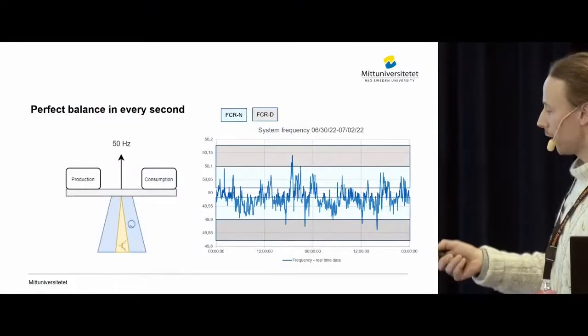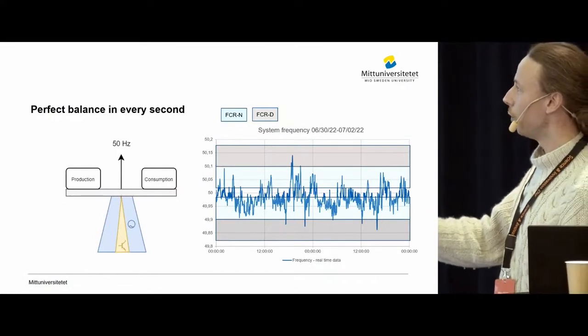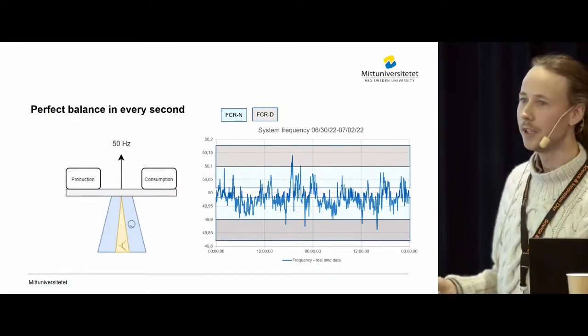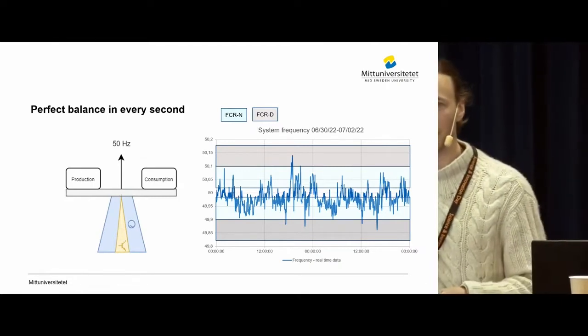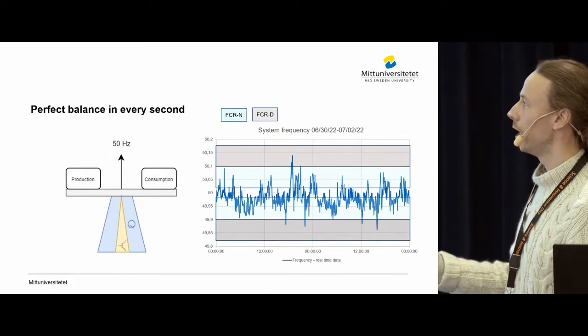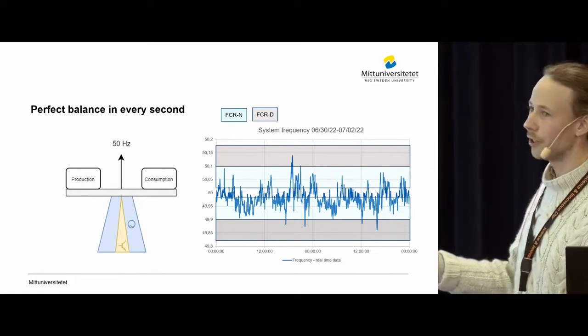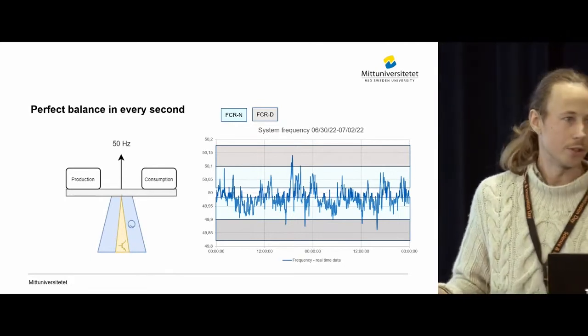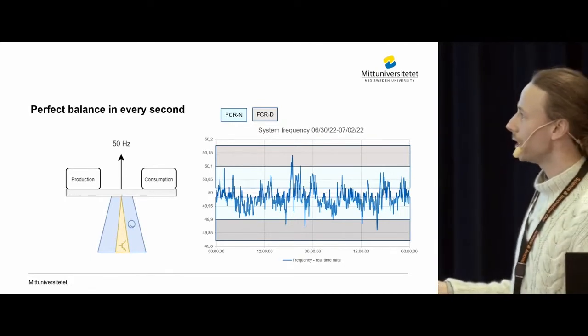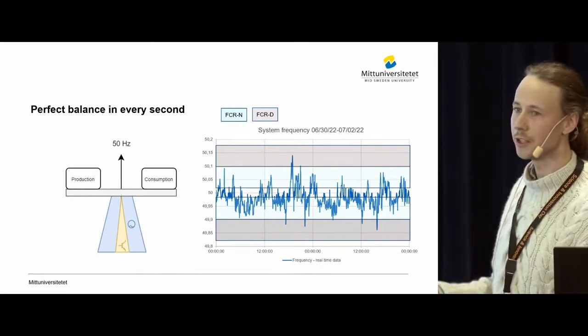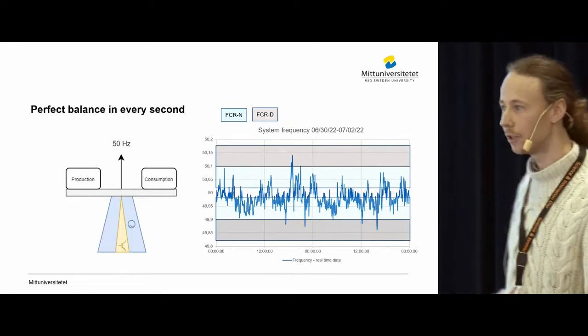We're talking about what's happening in the power system. We're getting more converter-based generation and less generator-based production. I've illustrated how this affects the change in frequency in this pedagogical scale with two different bases. A power system with lots of generators producing electricity has a wide base, so if there's a dip in production, the scale won't tip as fast. But with lots of converter-based generation, this base shortens, and the system needs to be balanced more actively and faster to counteract dips in frequency.